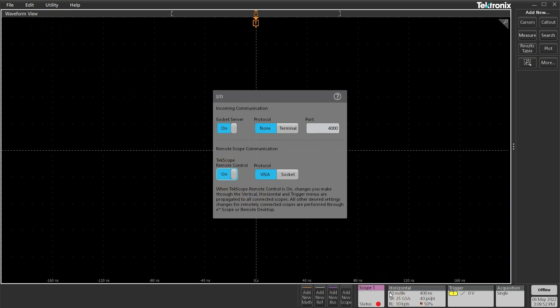This way, whatever horizontal, vertical, or trigger conditions I set in TekScope will also be directly done on the actual scope as well.